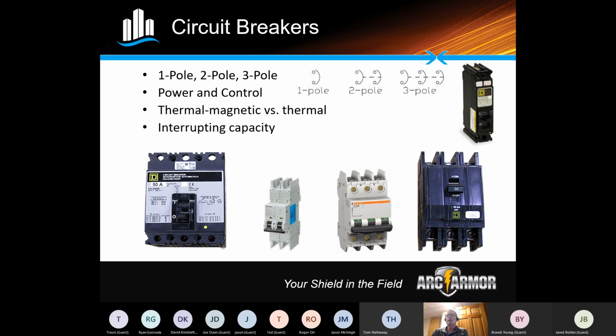Okay, moving on then. The other thing that you're going to hear with breakers is interrupting capacity. So I always like to throw out what the definition of interrupting capacity is. Basically, it's the maximum fault current that can be interrupted by a breaker without failure of the breaker. So you're going to hear terms when you're talking interrupting capacity of 5,000 amps or 10,000 amps or 42,000 amps, right? That is the interrupting capacity that a breaker can sustain without causing damage to the breaker or anything downstream.